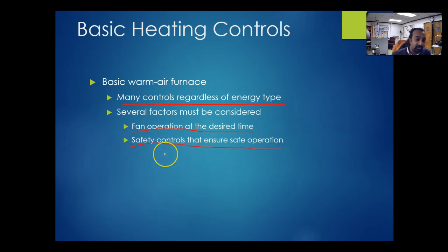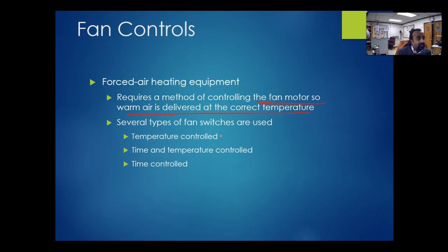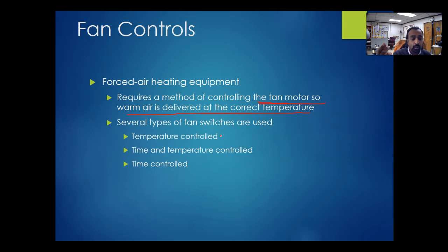For safety controls, you need to control when the heat comes on and off, especially with combustion, and prevent overheating of the air. Forced air equipment requires a method of controlling the fan motor so the warm air is delivered at the correct temperature and flow rate. There are several types of fan switches. In the energy systems lab, you'll get introduced to a stack-mounted relay — a bi-metal control that goes into the duct system to sense the temperature of the air.